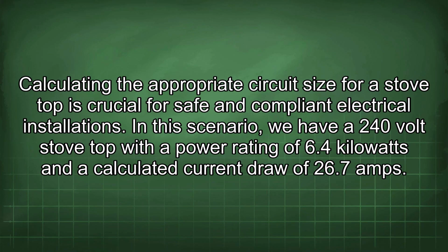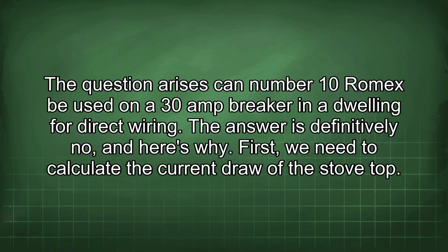Calculating the appropriate circuit size for a stovetop is crucial for safe and compliant electrical installations. In this scenario, we have a 240-volt stovetop with a power rating of 6.4 kilowatts and a calculated current draw of 26.7 amps. The question arises, can number 10 Romex be used on a 30-amp breaker in a dwelling for direct wiring? The answer is definitively no, and here's why.